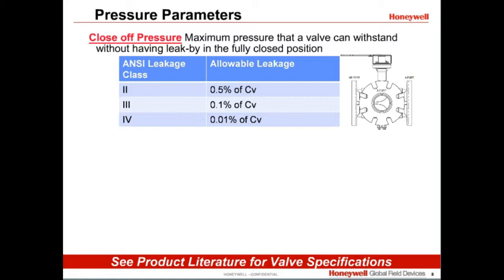With two-way valves, the valve must close off against the total dynamic pressure of the system. This is the pump discharge pressure minus the pump inlet pressure. If the total dynamic pressure of a system is not known, then use the pump pressure to be conservative.